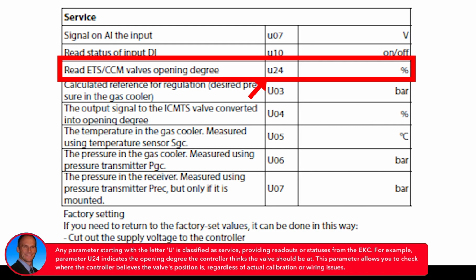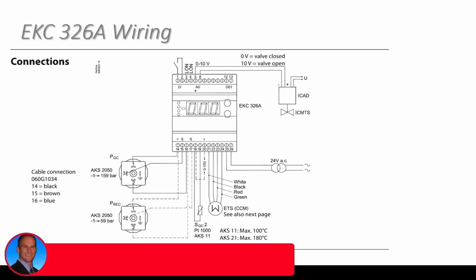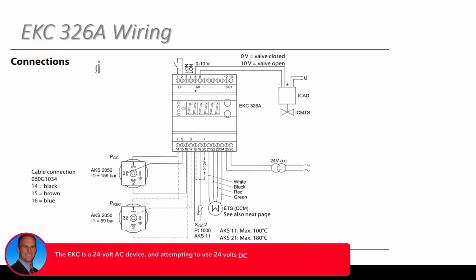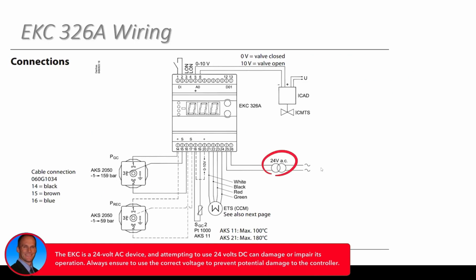So if we're saying 50%, but we're not wired properly on the leads coming off of the CCM back to the EKC, then it's very possible we could be fully closed or fully open when we think we're maybe at a 50% mark. Perfect. And then this EKC, last point I'll just touch on, pretty straightforward, but it is a 24-volt AC device. We get guys that maybe questioned or tried it without asking first, but if they try to throw 24 DC on here, it's a good chance you could kill the controller, or at a minimum not have it run properly. So yeah, it is a secondary 24 AC.